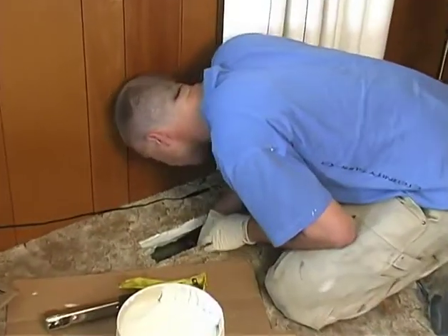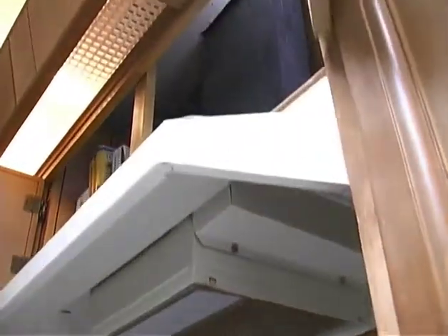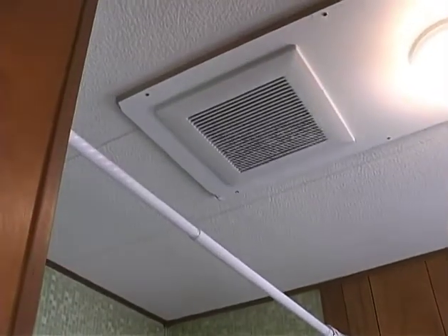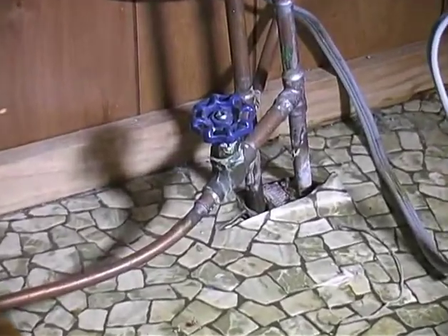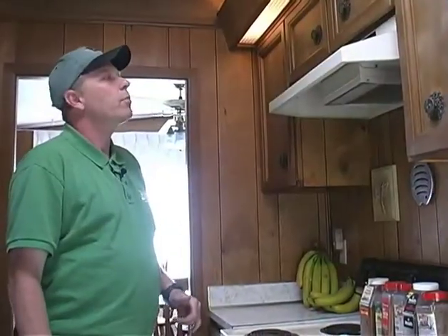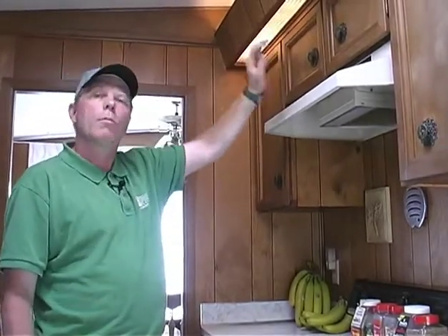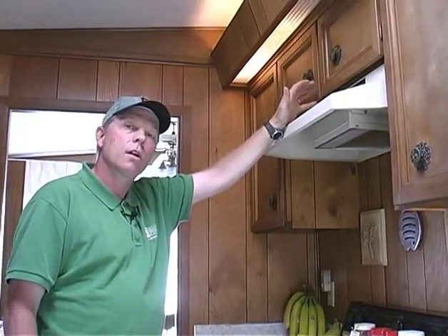Air leaks are found in a number of places in a mobile home. Some of the most common are in the ductwork, in the kitchen fan, around the bath fan, around skylights, possibly around plumbing penetrations. Let's take a look at a couple of these leakage sites. One of the first places I look for air leakage in a mobile home is high in the building envelope. There's a kitchen fan here, and the vent stack goes up into the attic cavity, and often there's a hole where it intersects the ceiling plane.